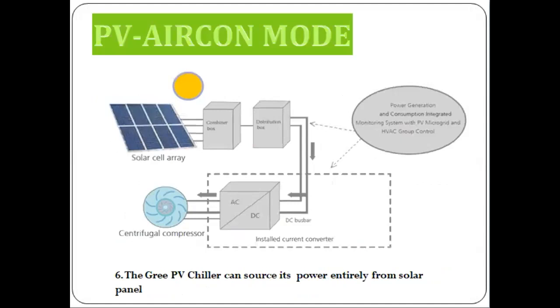Number 6, the GREE PV chiller can source its power entirely from solar panels. The PV-AIRCON mode indicates the mode where all the power generated by the PV system is used for the GREE PV chiller unit's operation. Please keep in mind that the PV system design capacity will deliver an average of 15 to 20% of its total capacity to any GREE PV chiller.